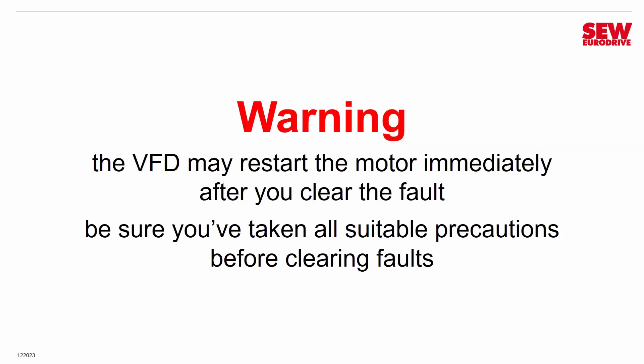Here's an important warning: depending on how you've configured the VFD, when you clear a fault the VFD may restart the motor immediately. Be sure you've taken all suitable precautions before clearing faults — otherwise the motor could start unexpectedly and somebody could get hurt or something could get damaged. You shouldn't have any problems if you take normal precautions. Motor restart behavior will be discussed in another session.